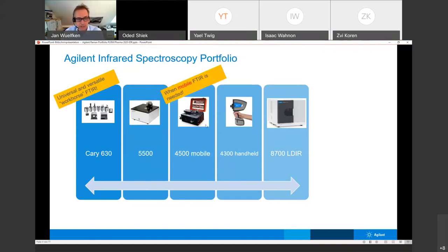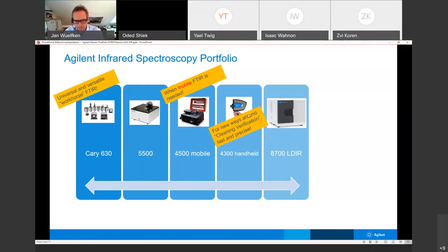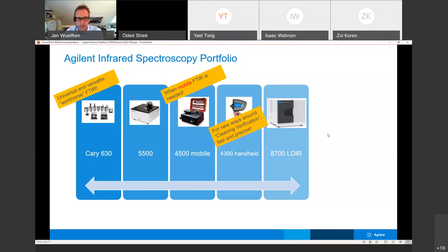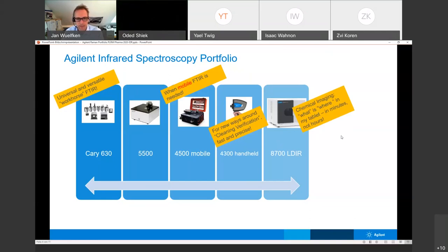We also have something around cleaning verification — a technique where we can do much faster cleaning verification of vessels. We measure the surface of the metal and can say there are two micrograms of your API still on the metal surface, or confirm the metal is clean so you can run your next batch. And we have chemical imaging where you can see what is where on a tablet — cut your tablet in the middle and see if the crystal size is not ideal or if the API is not well mixed. This can be done with a quantum cascade laser.